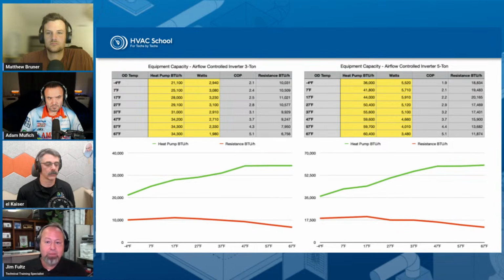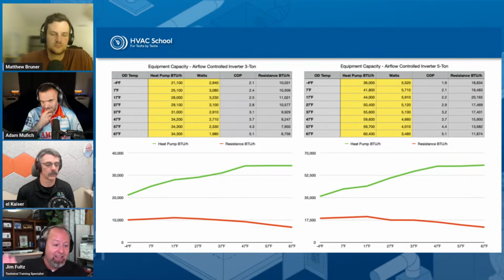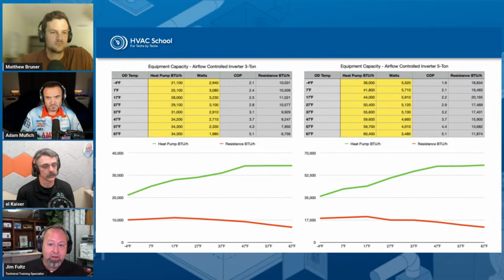And I can compare how many dollars or cents the heat pump's going to give for 80,000 BTUs at 47 degrees or 17 degrees, or in a chart that Eric's showing here, at any degree we would want to. You basically make another column and put on there how many gallons of propane it would take on an 80% efficient furnace to equal that same rate. Hopefully I didn't get too much in the weeds there, but there is a way to calculate the efficiency cost of that heat pump versus the backup heat.